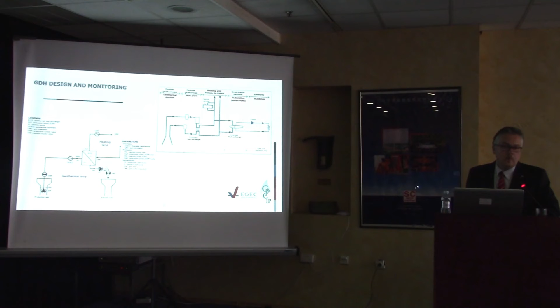How does a geothermal doublet work? We have a pump, a heat exchanger, a reinjection pump, and a filter, that's it. On the supply side we have the heat plant, then the heating grid, then a substation, and then the buildings. What's interesting is that every geothermal doublet has a backup boiler; in case the system goes down, the backup boiler takes over and supplies the heat.